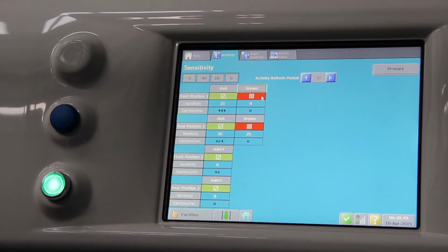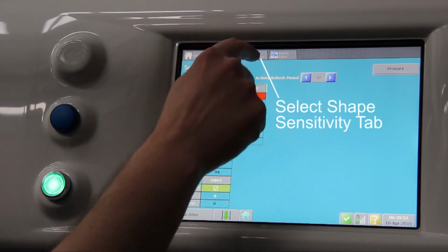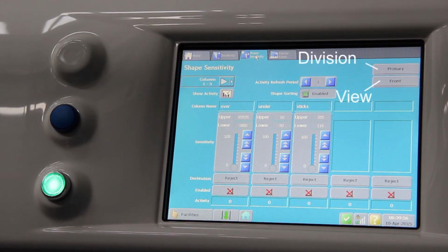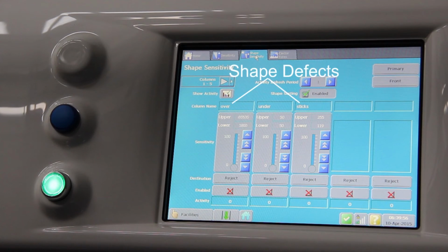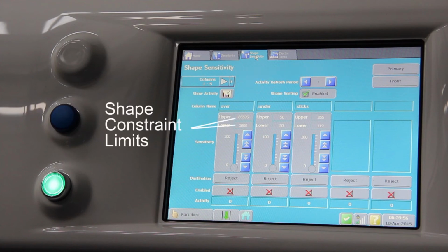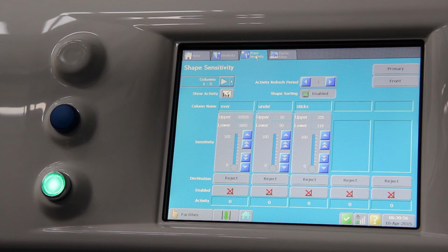If there is shape sorting available on the machine, there will be a Shape Sensitivity tab. Selecting the Shape Sensitivity tab will bring up the Shape Sensitivity screen. There can be shape sensitivity adjustments for each sort division and each view. Each column represents a shape defect definition, for example, oversize, undersize or stick-shaped. The upper and lower shape constraint limits will vary depending on the size, shape and type of defect. The units will also be dependent on defect type.